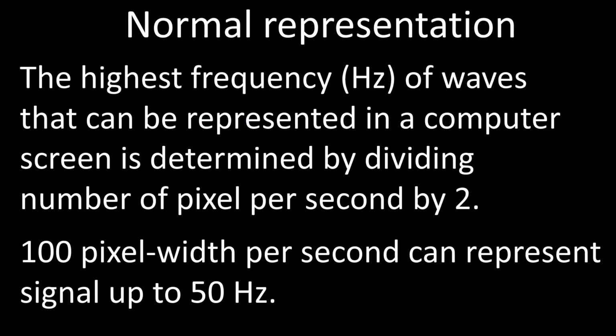It is important to understand that in order to get normal representation of the EEG activity, the highest frequency of waves that can be represented in a computer screen is determined by dividing the number of pixels per second by 2. For example, if a screen can accommodate 100 pixel width per second, it can represent a signal of 50 Hz. And in reality, even that it doesn't do too well. But that's the Nyquist number, so that's the one that you must remember.